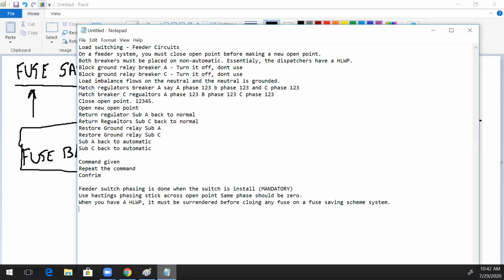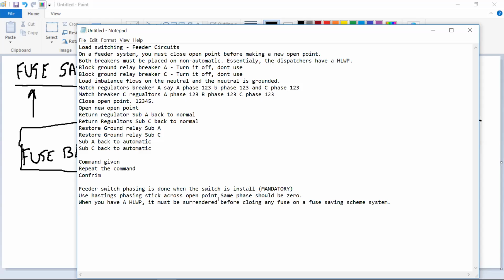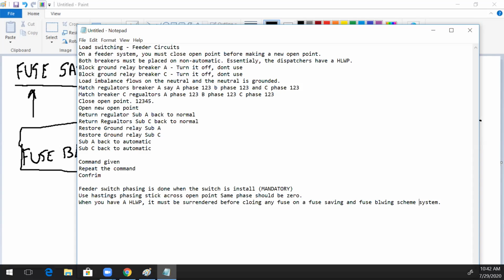Good answers out there. Okay, so when you have a hotline work permit, it must be surrendered before closing any fuse in a fuse saving and fuse blowing scheme. This is easily forgotten, guys, especially while you're going through the course of the work of the day, because you know you've got some safeguard going on while you're doing your work. And it simply is, we're done with our work, I'm ready for you to close the fuse, and they just closed the fuse and they got a bad transformer and locked the entire feeder out because they were on a hotline work permit. Take your time. Ask, is the hotline work permit surrendered? Can I close this fuse? Then they will advise you either yes or no.